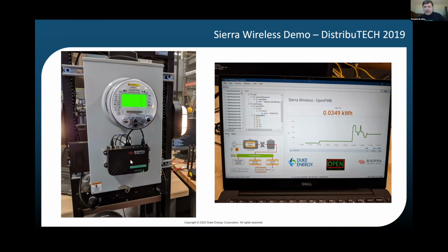We were publishing data once every second. Every time we polled the meter, we'd publish the data once a second, and it would send it out the cell modem. You'll see the radio antenna right here, going through another cell gateway into this laptop, where applications would subscribe to the data being delivered. You could see some of those real-time measurements displayed up here, so you could drill down into all those different measurement data structures.